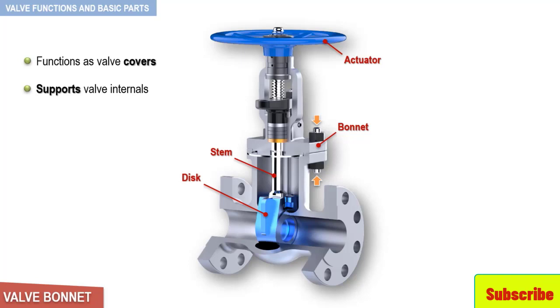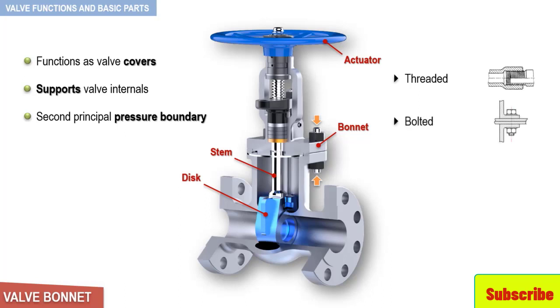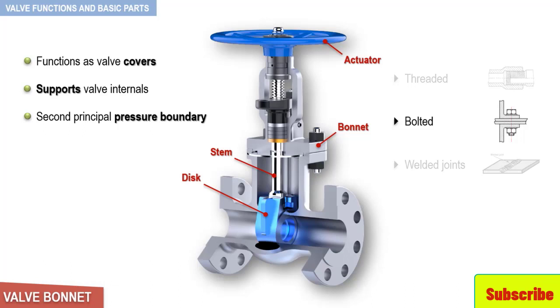The bonnet is the second principal pressure boundary of a valve. It is cast or forged of the same material as the body, and is connected to the body by a threaded, bolted, or welded joint. In our example, the bonnet is connected to the body by a bolted joint. In all cases, the attachment of the bonnet to the body is considered a pressure boundary, meaning that the weld joint or bolts that connect the bonnet to the body are pressure-retaining parts.